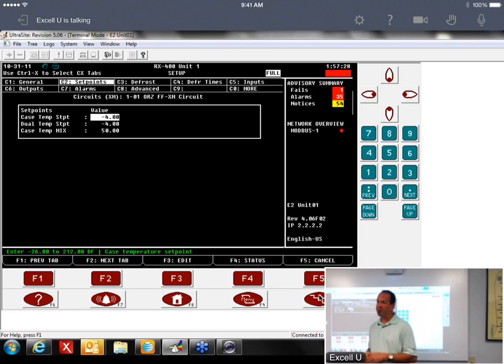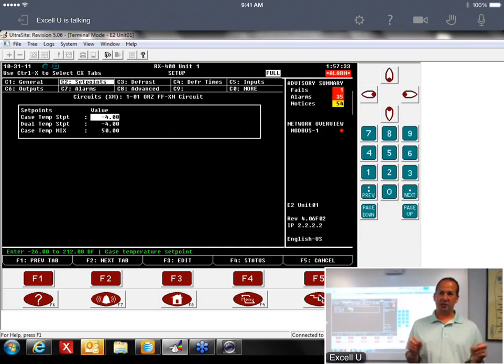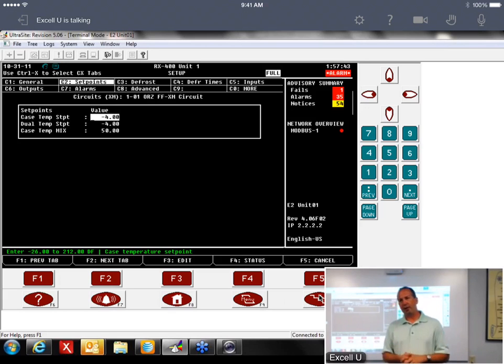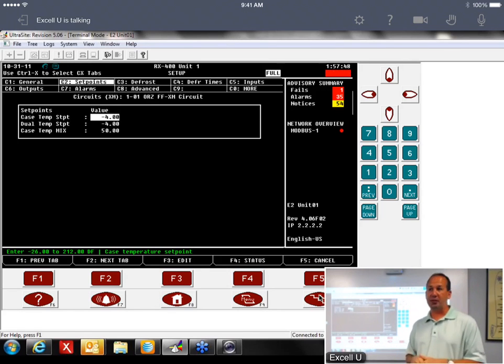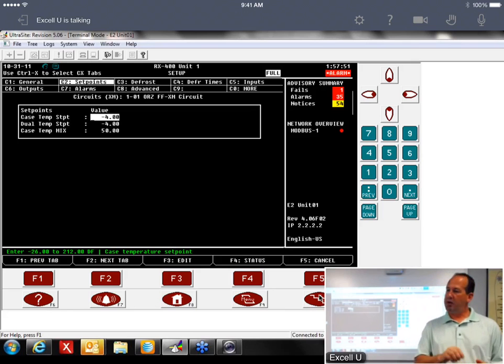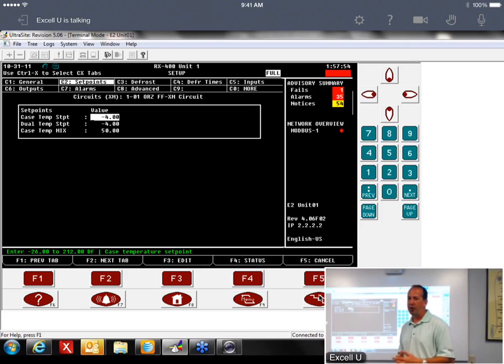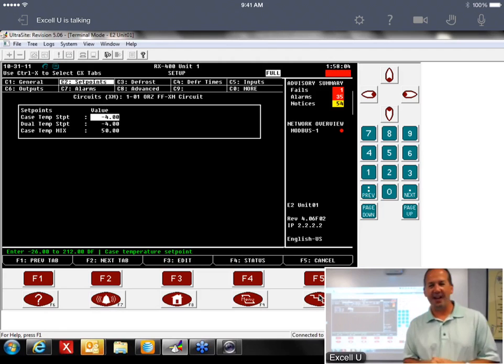So if you change that to -4, which is 1 degree below what the case temp setting should be, it actually averages out to -3, because now it'll go -4, it'll come on, it'll shut off at -2, and your average case temp will be -3. So that's one of those things. I'm addressing it with all the Publix people so that they know that, because I know a lot of them are by the book. So no, Hill Phoenix says it's -3, it's got to be -3. Well, your end result's going to be about a degree average higher than what you want. So that's again one of the little idiosyncrasies.